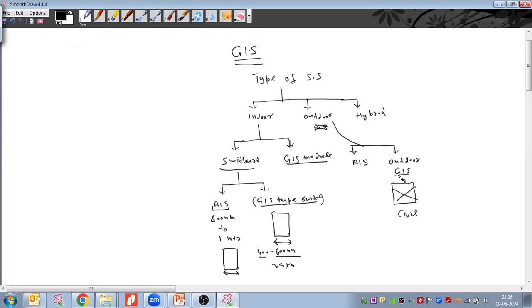So when purchasing the GIS as a design engineer, we have to inform the manufacturer whether we are taking the GIS indoor type or outdoor type, because the module construction and the ingress protection IP class change from indoor to outdoor. Even though we say GIS, we have to write GIS indoor installation, because GIS could be outdoor as well. Outdoor could be AIS or outdoor GIS.